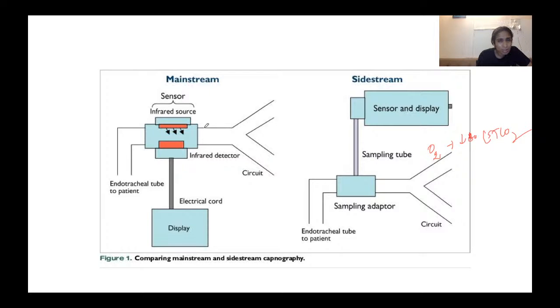Then in this monitor, there are fewer disposable items. Nothing much to dispose in this, so it is more economical also. Now disadvantages are, this has to be placed near the patient, and first of all it is so heavy, because to obtain an accurate reading, it has to be placed near the patient, and because of its bulky nature, it can cause kinking of the tube. Then it increases dead space. The adapter between the patient and the breathing system increases dead space because it is bulky.